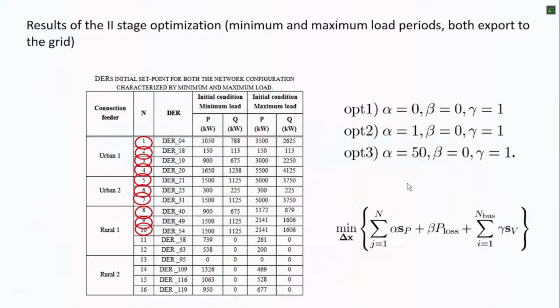In the second way, we consider both the voltage and respecting the active power of the previous day equally, with the same coefficients. The last one is a strange case where we weight the power of the previous day heavily, but we can also move the reactive power, so we use practically only the reactive power and the tap changer to control the voltages. I recall again the objective function.